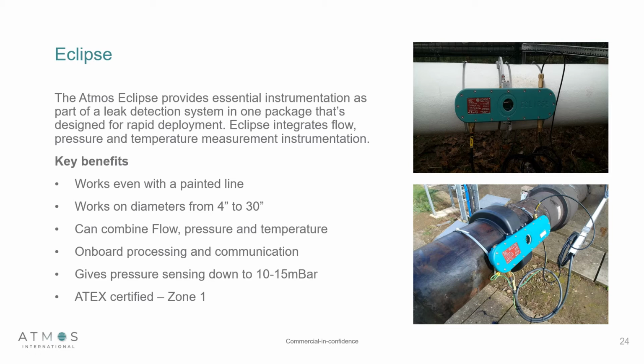Of course, it uses non-intrusive pressure, which means it's not as accurate as an intrusive PT, but we're still able to see pressure changes down to 10 to 15 millibar. So that's around 0.015 bar of change, meaning it's still sensitive enough to provide reliable leak detection and even theft detection. As well as being ATEX Zone 1, it's IP68, and it's also passed its test to be buried. So this Eclipse unit, if you want to prevent it from being tampered with, can be buried to a depth of 2 meters.